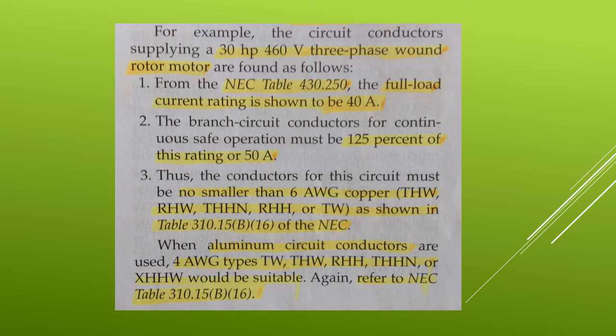For example, the circuit conductors supplying a 30 horsepower 460 volt three-phase wound rotor motor are found as follows. These steps are on the screen. Step 1, from the NEC table 430.250, the full load current rating is shown to be 40 amps. Step 2, the branch circuit conductors for continuous safe operation must be 125% of this rating, or 50 amps. Step 3, thus the conductors for this circuit must be no smaller than 6 AWG copper, THW, RHW, THHN, RHH, or TW, as shown in table 310.15(B)(16) of the NEC.